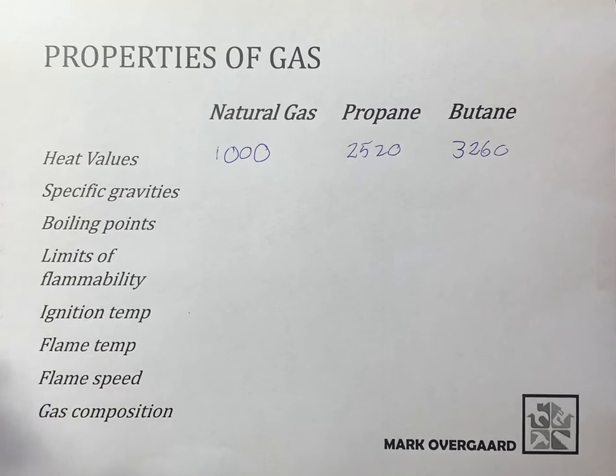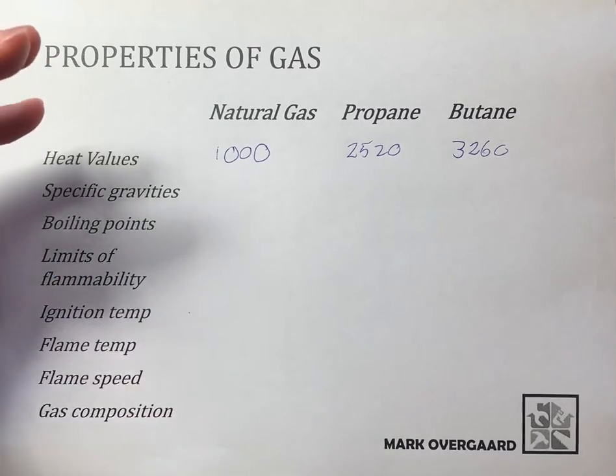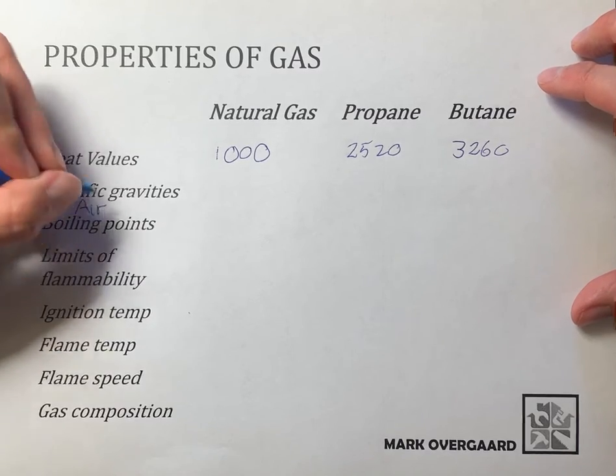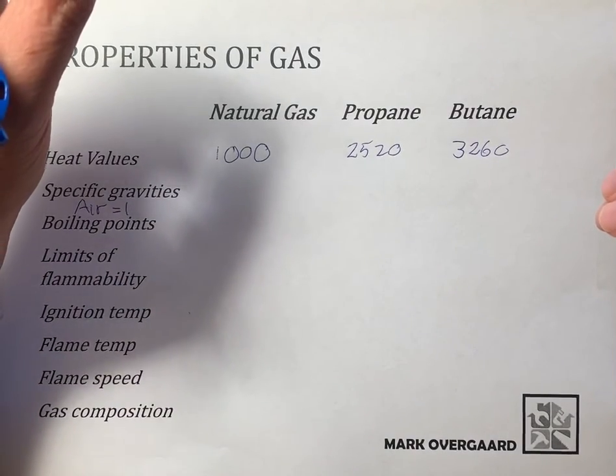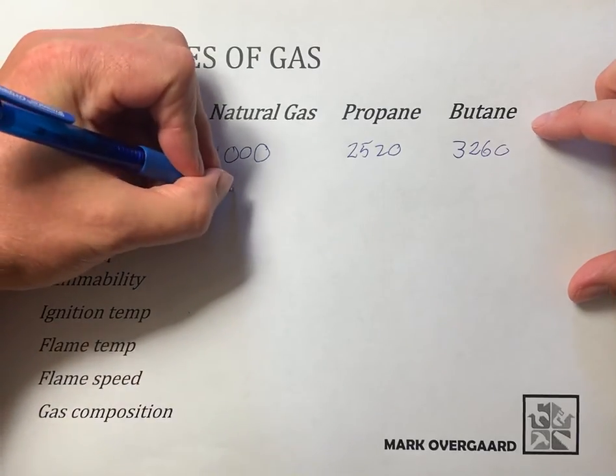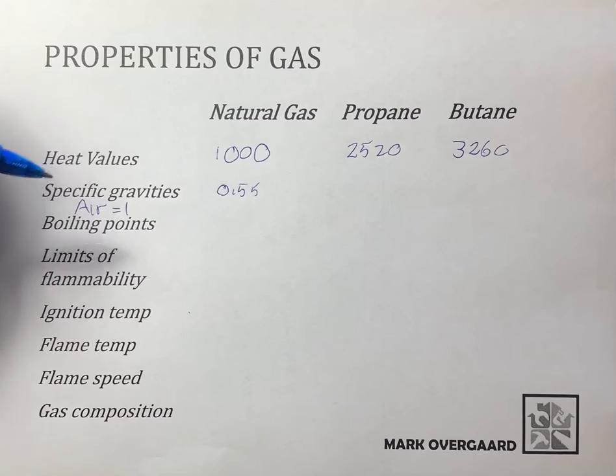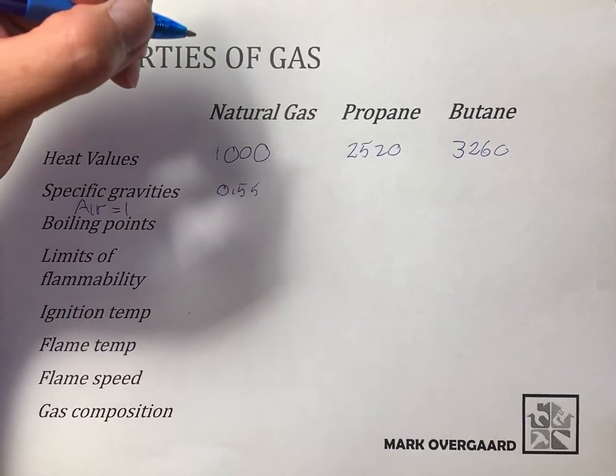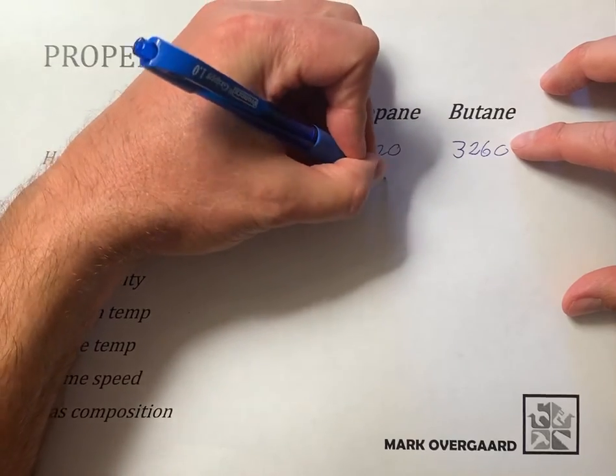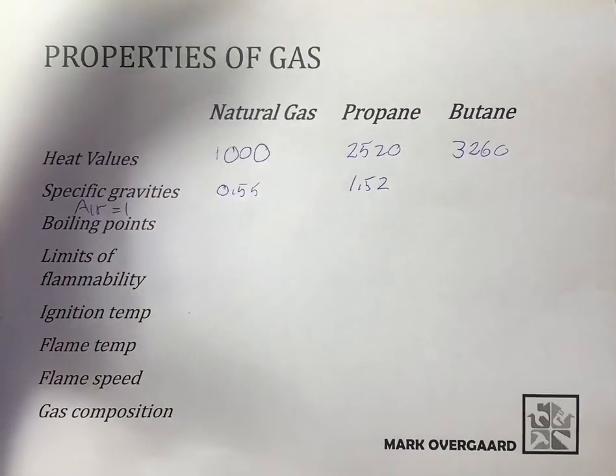Next, specific gravity — we're dealing with the vapor state here. Air is our starting point, and air equals one. If a gas is lighter than air, it has a specific gravity, or relative density, of less than one. For natural gas it's 0.55, which indicates it's lighter than air. Propane vapor is heavier than air at 1.52, meaning if propane escapes it will congregate on the floor or below the air, which can cause a lot of safety problems — there are code clauses that relate to that. Butane is even heavier at 2.